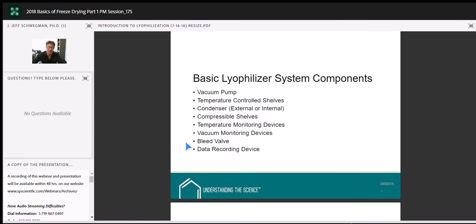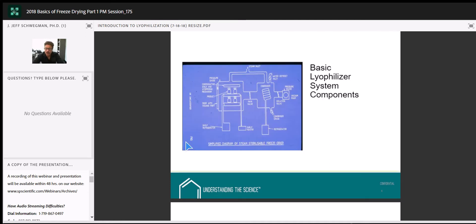Basic components of a freeze-dryer. This is what's called an external condenser freeze-dryer: a separate chamber for the samples and a separate chamber for the condenser coil or plate. The two chambers are connected by a tube called the throat. In most cases we'll have a butterfly valve in there that we can open and close — one of the tools we use during cycle development to help understand the endpoint of primary drying.